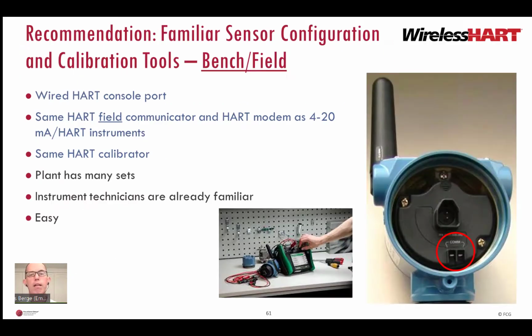Again, be careful. WirelessHART solves this with a wired HART console port. The HART tools almost all plants have today can be connected to this console port. HART field communicators, HART modems for laptops, and portable calibrators. This is ideal for configuration, function check, and calibration on the workbench or in the field.